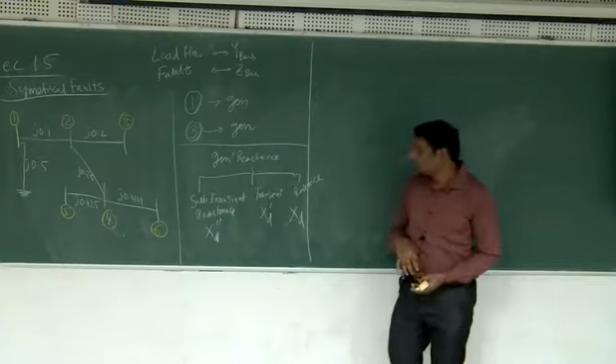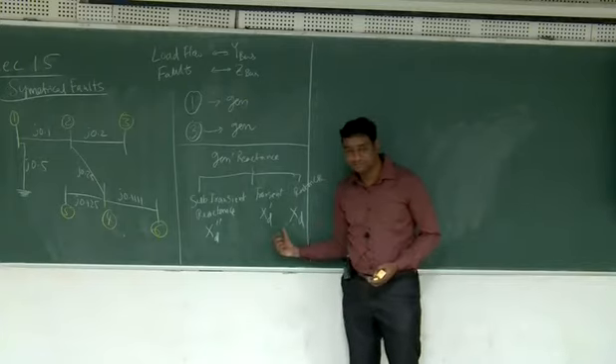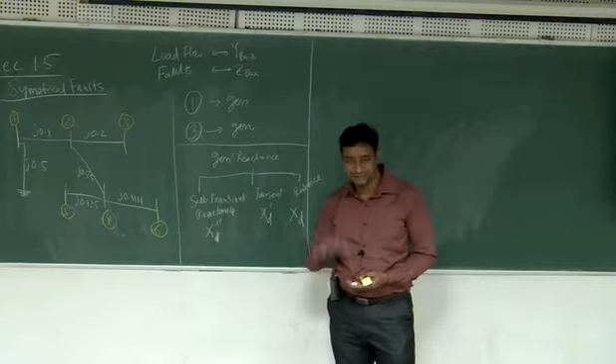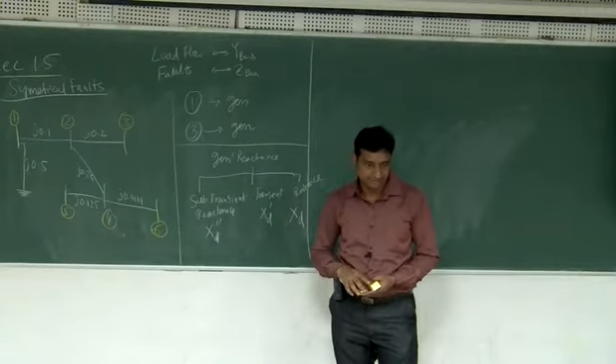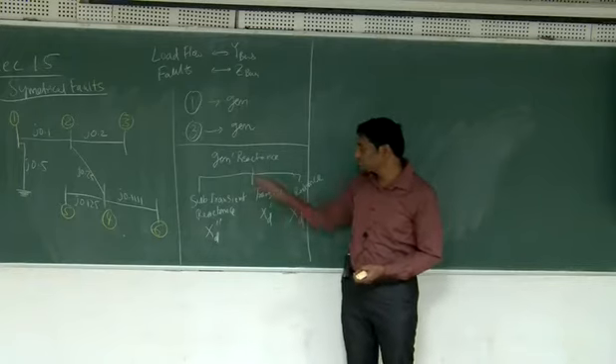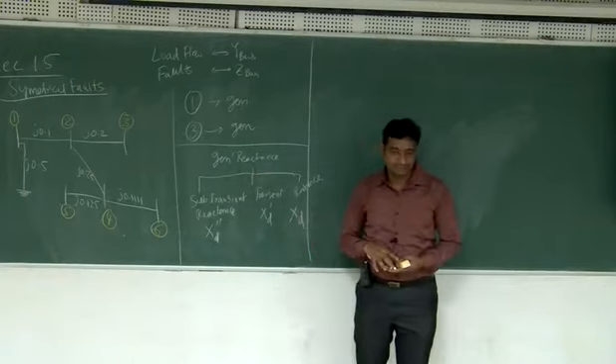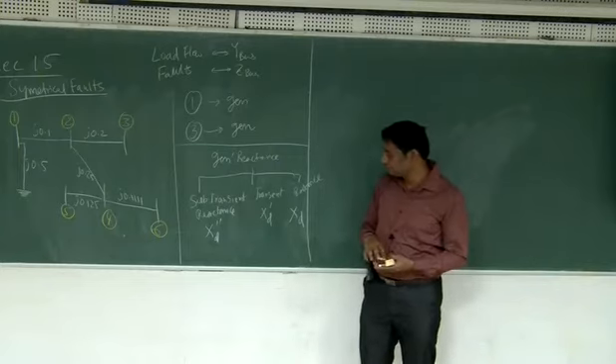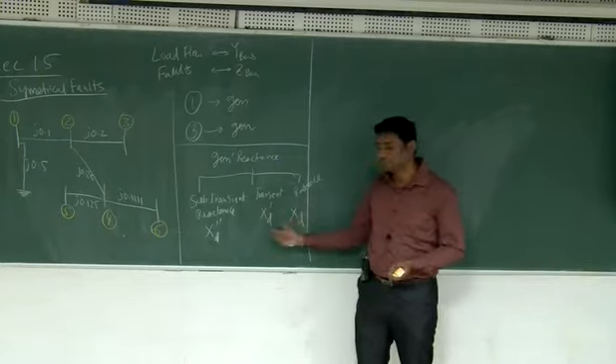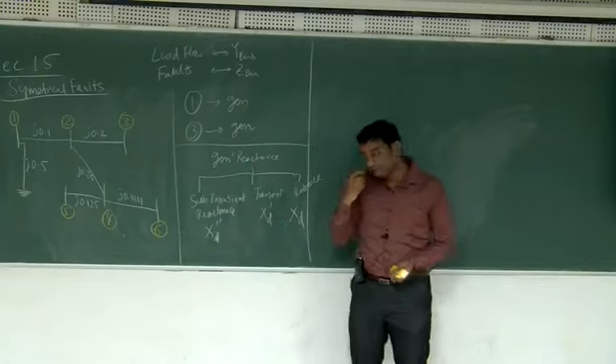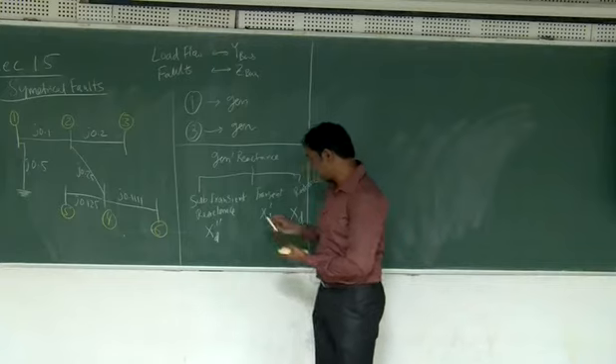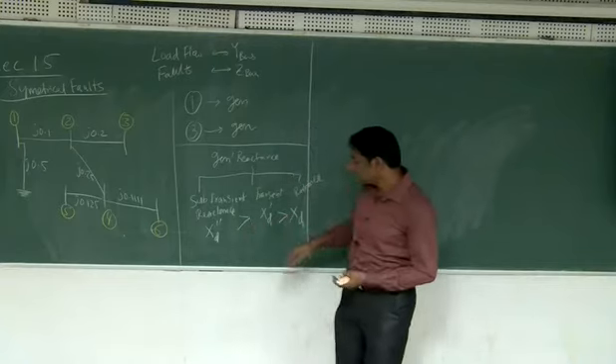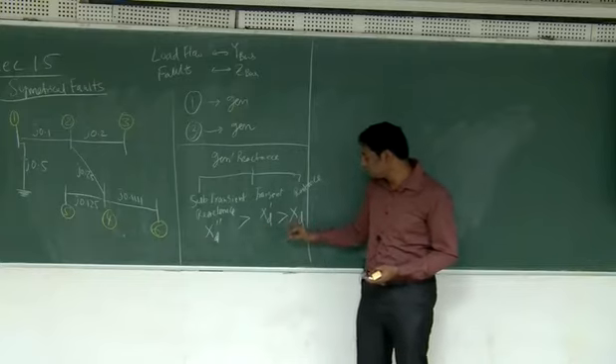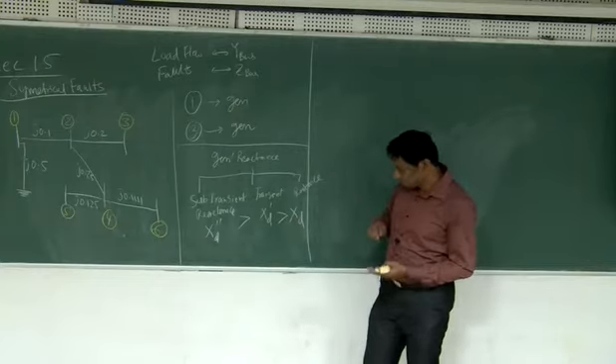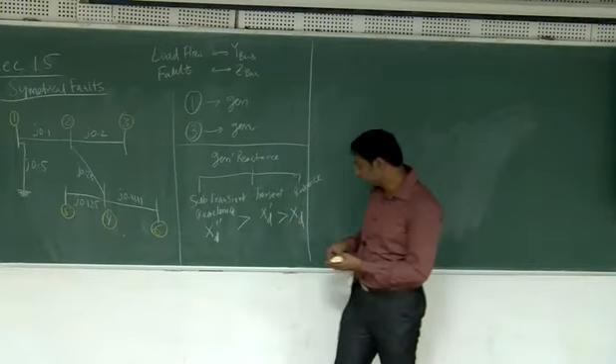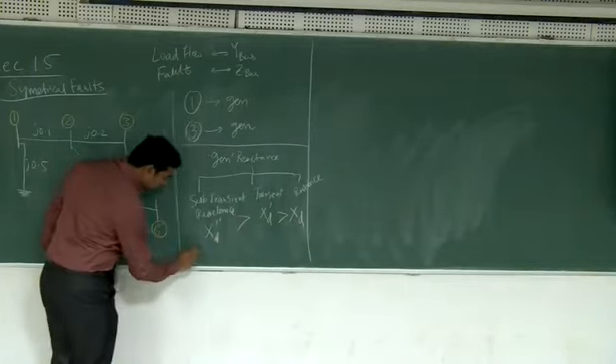So why are these 3 different types of reactances there? That has something to do with the construction and the design of the machine itself. The synchronous machine, and a generator means it's a synchronous machine, is designed in such a way that it will exhibit 3 different values of reactance. Usually the design is such that the value of XD double dash is greater than the value of XD dash, which is greater than XD. And how to determine which one to use? The general thing is, this is like up to 2 cycles.